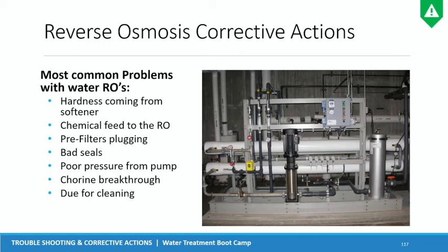It's good to make sure that you don't have chlorine getting through that carbon, because at some point the carbon is going to go bad and it has to be replaced too. And that's a lot cheaper than replacing membranes. Or does your RO need to be cleaned?